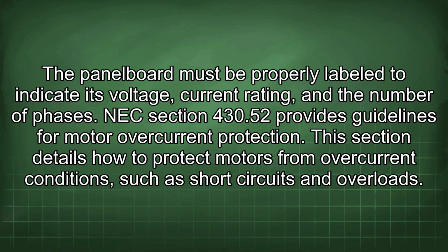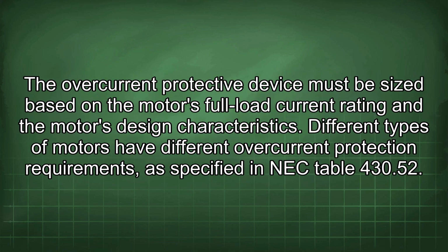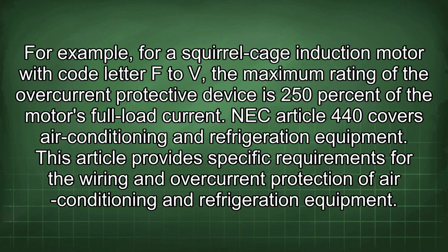NEC Section 430.52 provides guidelines for motor overcurrent protection. This section details how to protect motors from overcurrent conditions such as short circuits and overloads. The overcurrent protective device must be sized based on the motor's full load current rating and the motor's design characteristics. Different types of motors have different overcurrent protection requirements, as specified in NEC Table 430.52. For example, for a squirrel cage induction motor with code letter F to V, the maximum rating of the overcurrent protective device is 250% of the motor's full load current.